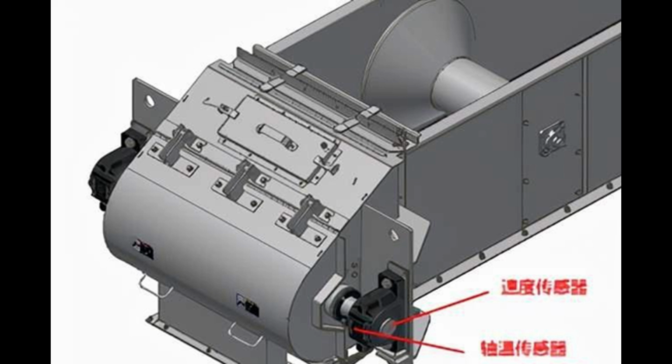When the infrared sensor is used, the sensor emitting hole should be aimed at the end cover, tile seat, of the main drive drum bearing, and when there are two sets of driving devices, the temperature sensor is installed on the bearing end cover of the main drum bearing far away from the unloading drum. At the temperature measurement point, the device will alarm when the temperature exceeds the specified level, and the automatic sprinkler device will be started at the same time. With a belt with two drives, the sprinkler must be mounted on the same drive drum as the overtemperature protection device. 8. Coal pile protection device.